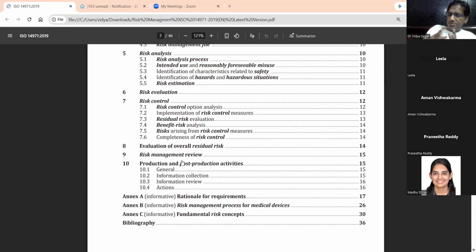Okay, because both devices are similar, with the same intended use, the technical, biological and clinical equivalence is the same. Then why is your device having new complaints or a different type of complaints, where your predicate doesn't have? Of course, there are a lot of other things that could contribute, but it needs to be looked at at a very microscopic level, dive deep and see, because new complaints should not arise.